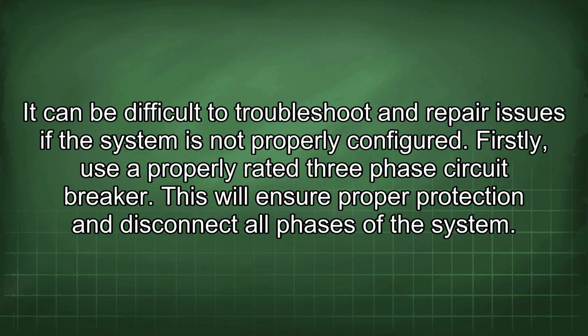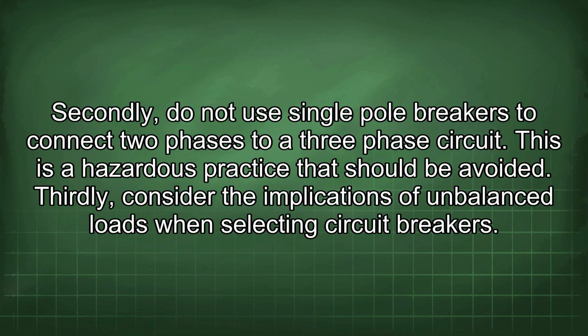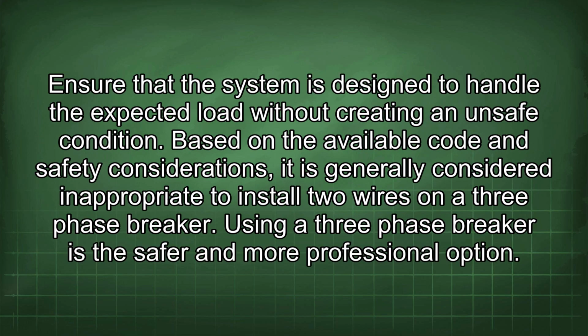Firstly, use a properly rated three-phase circuit breaker. This will ensure proper protection and disconnect all phases of the system. Secondly, do not use single-pole breakers to connect two phases to a three-phase circuit. This is a hazardous practice that should be avoided. Thirdly, consider the implications of unbalanced loads when selecting circuit breakers. Ensure that the system is designed to handle the expected load without creating an unsafe condition. Based on the available code and safety considerations, it is generally considered inappropriate to install two wires on a three-phase breaker. Using a three-phase breaker is the safer and more professional option.